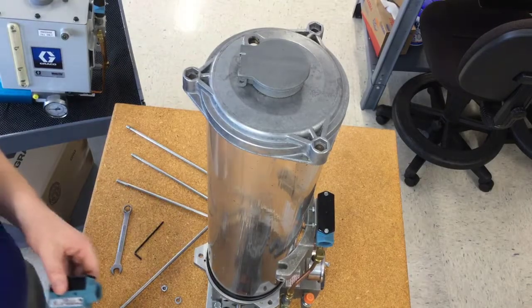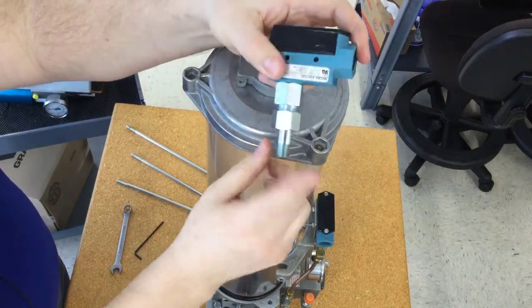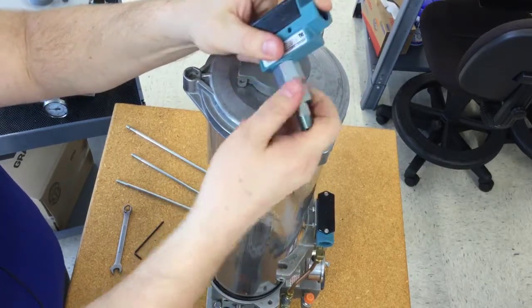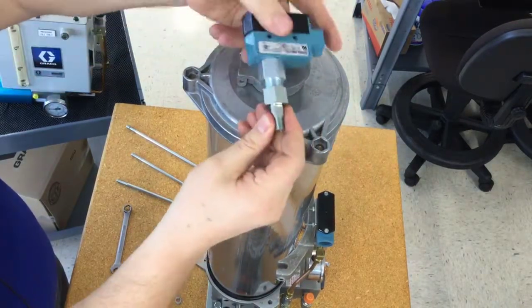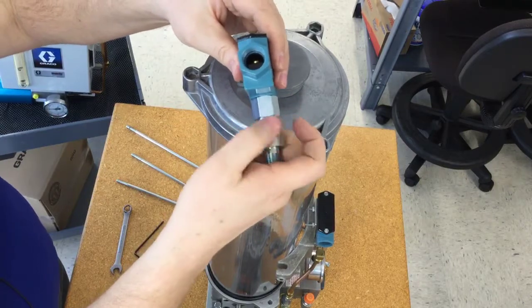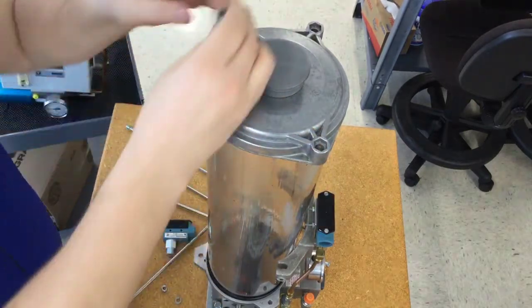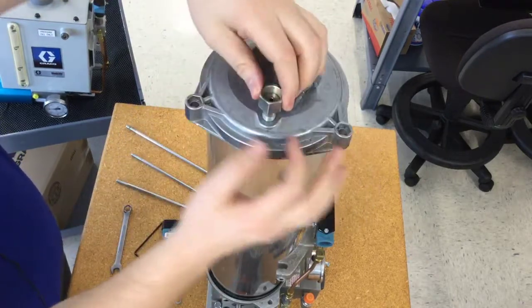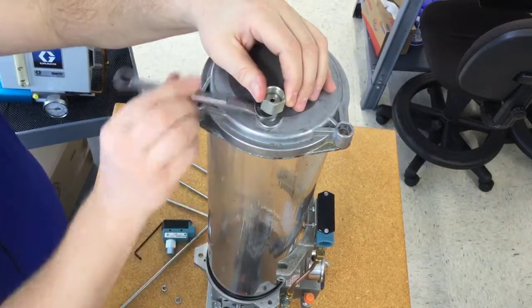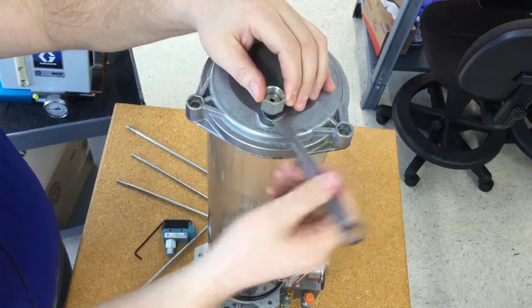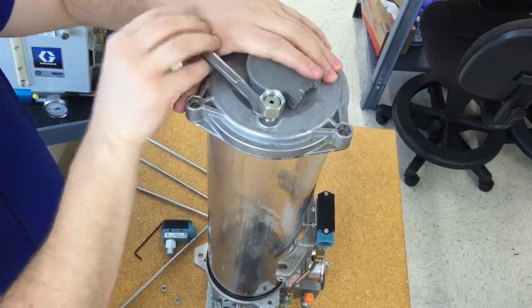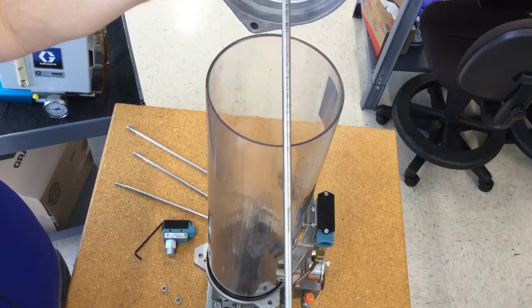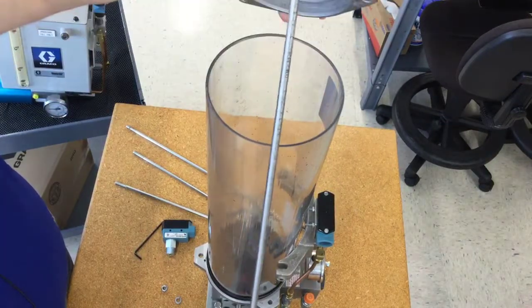Now let's take a look at how to install the toilet tank type of switch. A key detail here is that there's a flat on this round part for a half inch wrench, so you can use a half inch open end wrench to tighten that. This piece comes apart here so this is all able to spin which allows you to orient the switch however you want it. So these two pieces here now are what we're going to take over here to put into the top of the reservoir cover. I'm just twisting that into that quarter inch threaded hole. So now we can get that tightened in there.